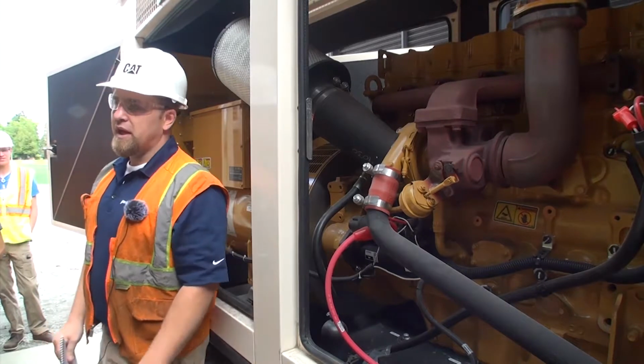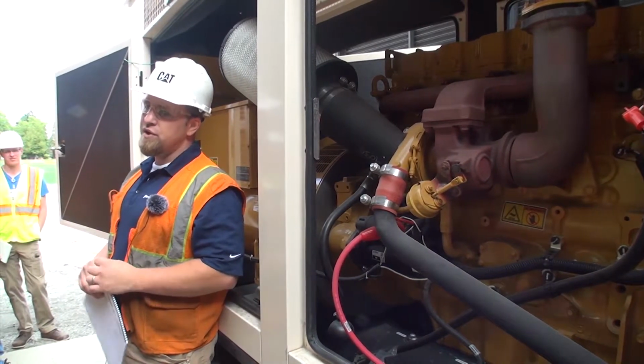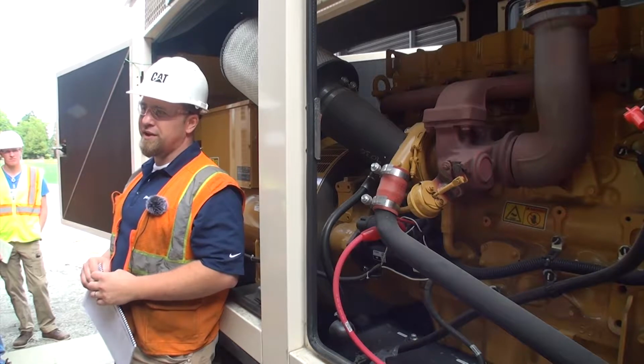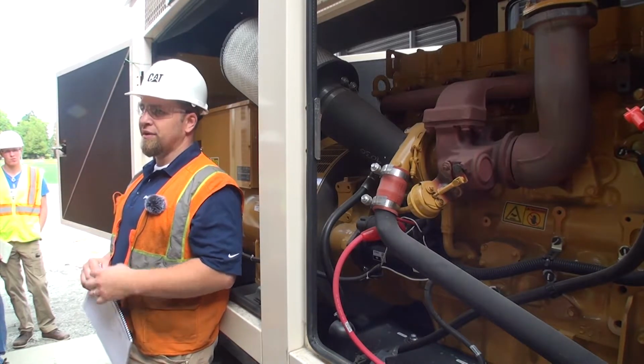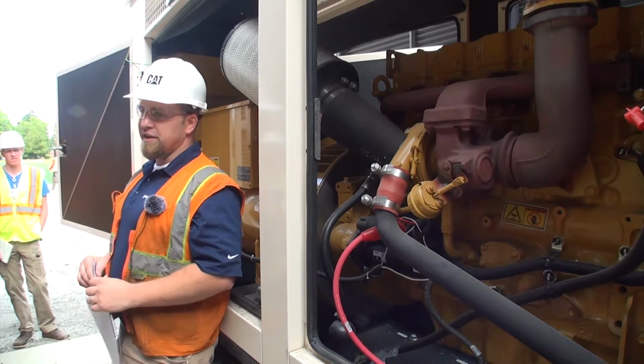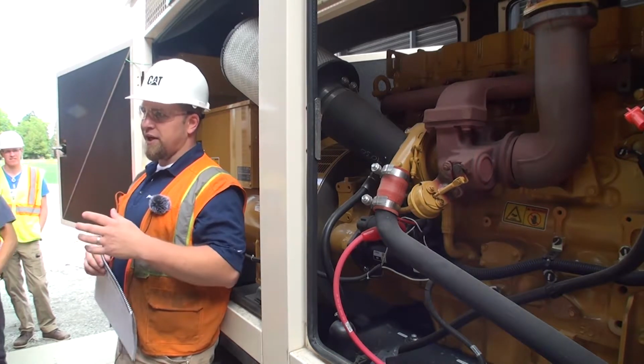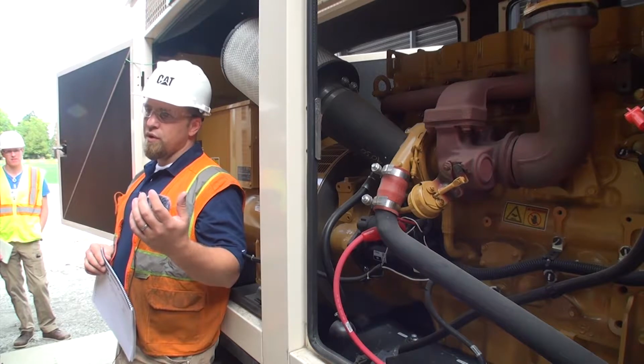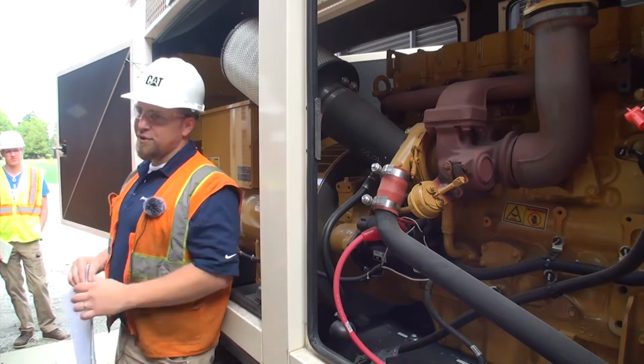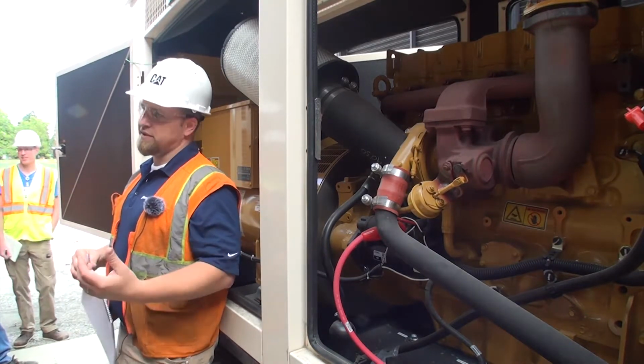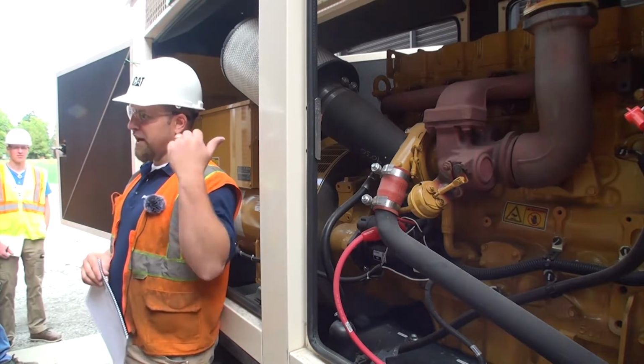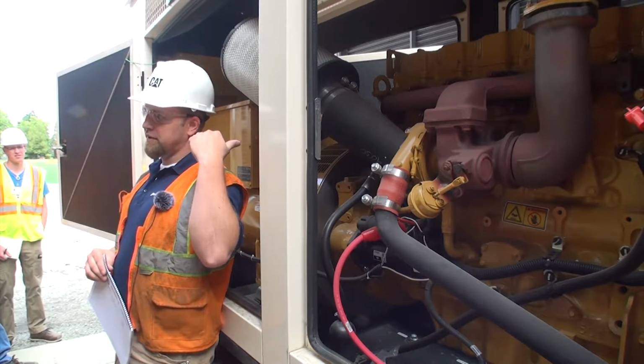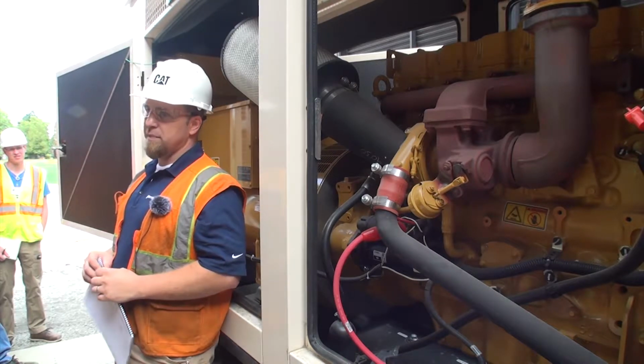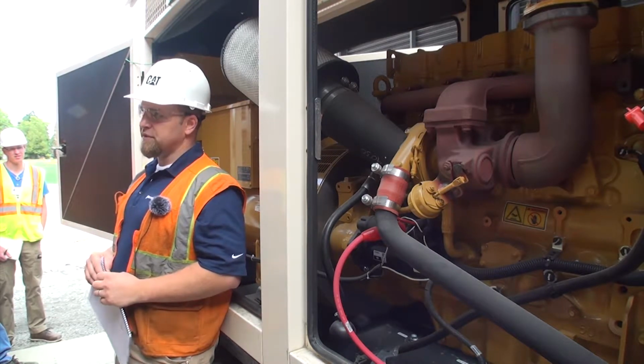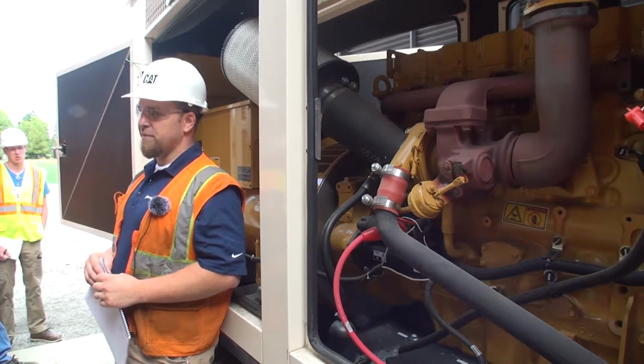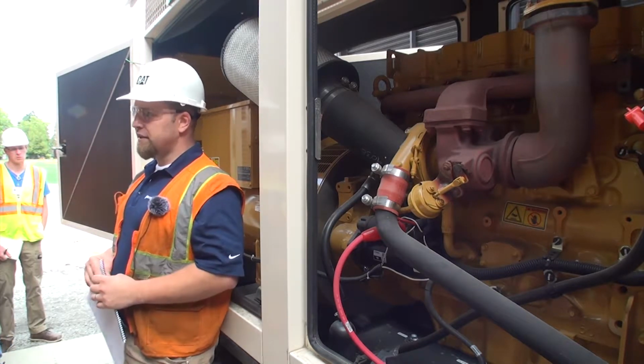How often do you do it? As recommended, usually we do it during our cooling service every 3 years, but really it's as recommended. With a unit like this it's pretty cheap, but once you get into bigger units, the reason I bring up annuals is you're talking about 110 gallons of oil versus about 7 here, so in comparison it's not that much, but it's still an option. The air filters on this one are usually 40 to 50 bucks, but on the bigger units they're about 160 a piece, and sometimes you have 4 to 5 of them, so it adds up when you're doing them every 3 years compared to just as needed.